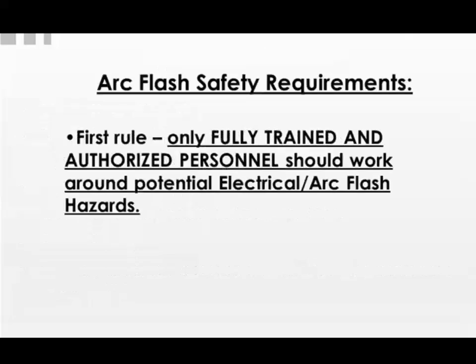Okay, the first rule that you should have in your company is that only trained and authorized personnel who are fully trained should work around potential electric arc flash hazards. That's the bottom line. Unless you are certified, your training is done, and you've got your program in place, ideally you should have done, or hopefully after this training you will have, an arc flash hazard analysis or hazard evaluation done to identify the hazards. You don't want your workers exposed to that. And you certainly don't want unauthorized personnel in the area. And that gets into restricted, limited, and different approach boundaries, and we'll be talking about that in a little bit. But the idea being that anyone that isn't trained and authorized and that's not equipped with the arc flash PPE should not be around that area.